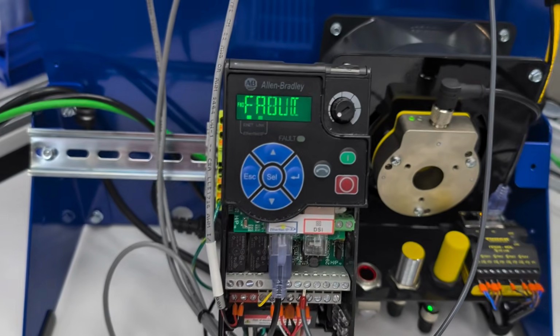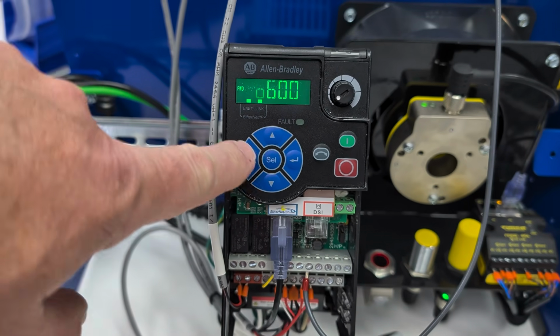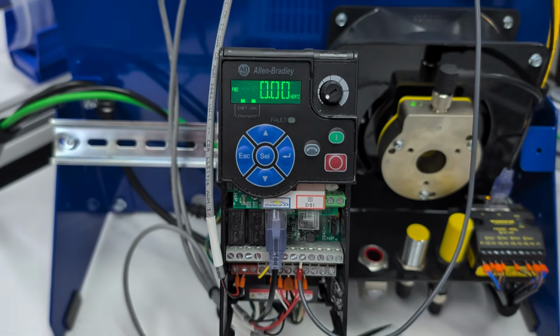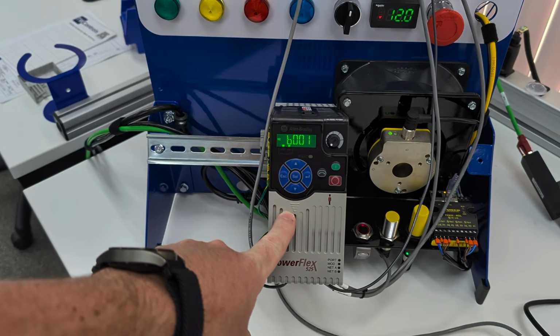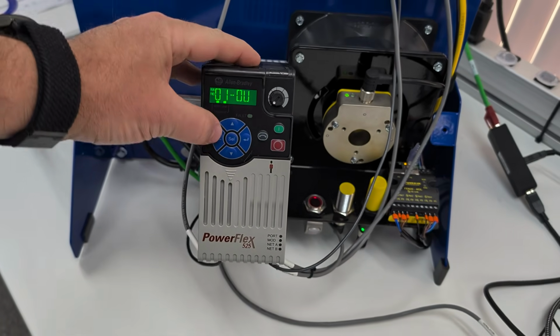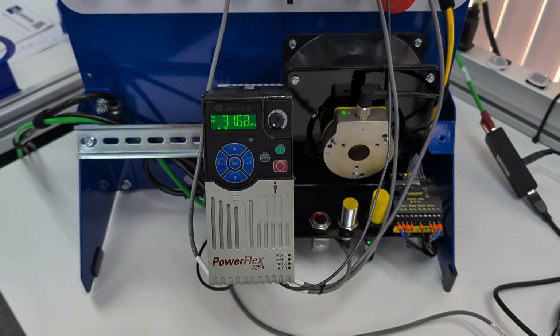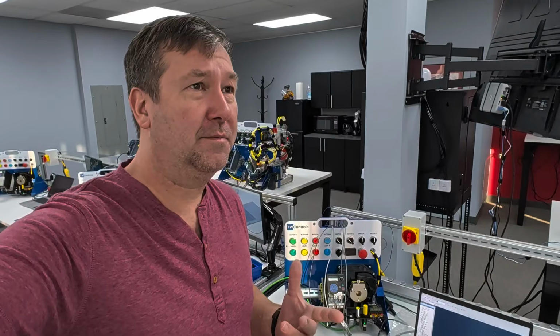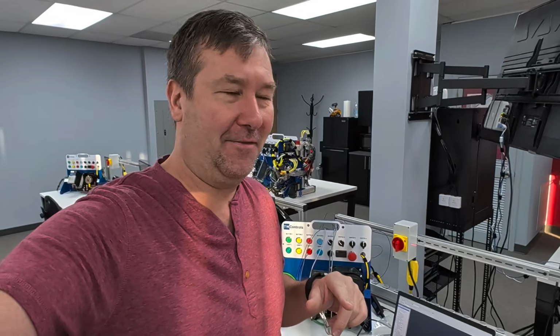Yep, on pretty much all of the drives. Well, why aren't you faulting? Well, you have a different fault. He was digging into the fault code, which coincidentally, the one across from it did not fault either. It seems fine. So, two things: I've got to figure out what the root cause is, and also I've got to figure out if it's worthwhile to replicate it.